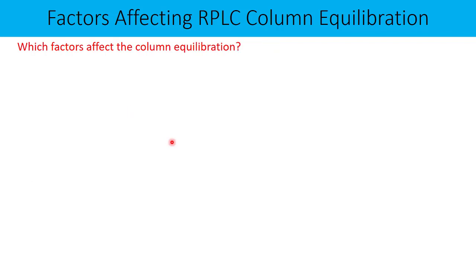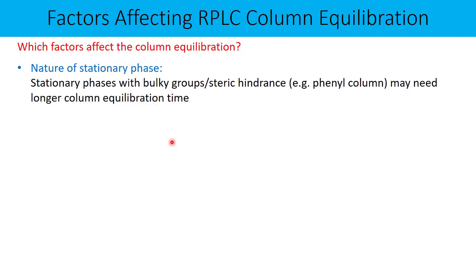Let us now understand which factors really influence the column equilibration process. You must have heard that at least 10 to 20 column volumes are required for proper column equilibration. The first factor is the nature of the stationary phase. Stationary phases with bulky groups like phenyl may need longer column equilibration, because these bulky groups will resist the passage of your mobile phase throughout the stationary phase, resulting in a longer equilibration time.